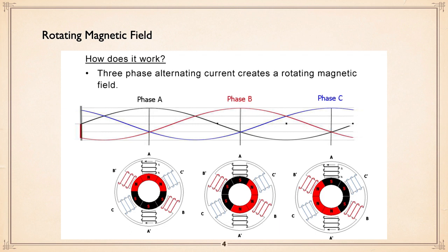And a couple of interesting comments. If you took a compass and put it inside that magnetic field, it would go around and around at 3,600 RPM counterclockwise. Now, that magnetic field that's created is not only in the motor, but some of it is outside the motor. We had a case where a service fellow of ours, back before credit cards used radio pinging, with a straight magnetic strip, about every other month had to get a new Visa card. Finally he figured out that he was leaning against 100 horse motors while they were running, and of course the magnetic field on the outside of the motor was busy wiping out the credit card.